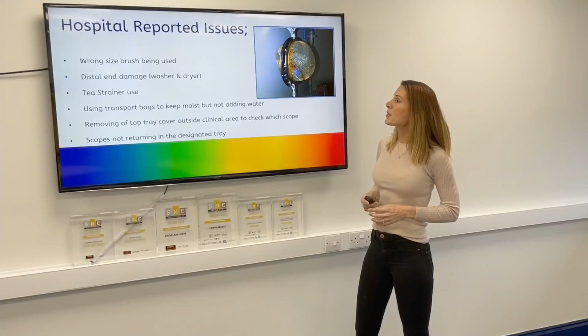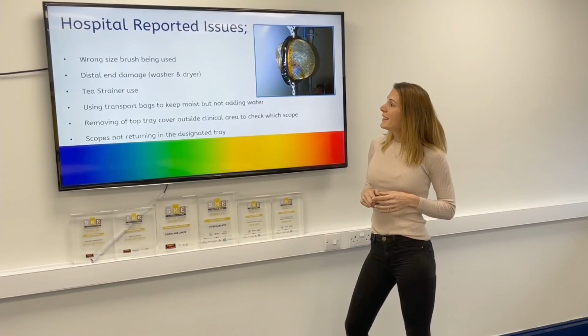So I spoke to some of my contacts in the hospital, some people that we work with, and I said to them, what are the biggest problems in your department? What do you see? And a lot of these concepts were the same across multiple hospital sites in the UK. So endoscopy decontamination technicians using the wrong size brush. What's the issue with this? Damage to the internal lumens, and frequently the brush getting stuck in the endoscope lumen, causing endoscopes to be taken out, having to go off to be repaired.